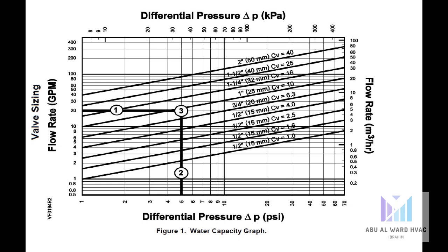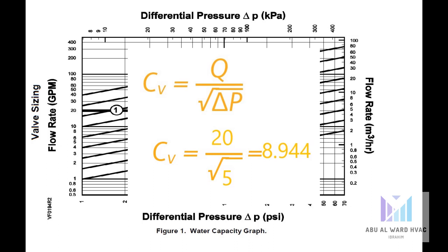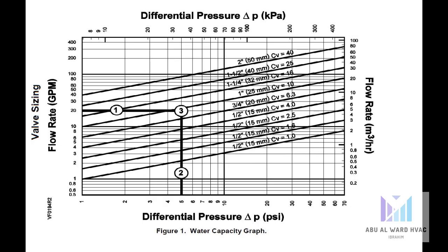First, we know the specifications. Next, we go to the valve sizing steps using the sizing chart. We take the flow in GPM and the valve differential pressure ΔP, locate them on the chart, and read off the Cv value. Applying the formula, we get Cv equals 8.9; the nearest higher value is 10, so Cv is 10. Therefore we select a one-inch valve.